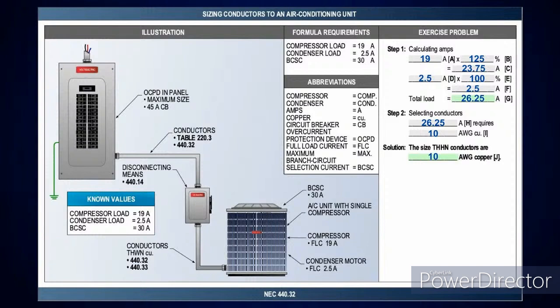Now remember this. You're going to still take one motor at 125% and all the rest are added at 100%, which you'll really see in the next illustration. So the largest motor here is the compressor. I'm going to take it at 125%. That'll give me 23.75 amps. Then I'll take the condenser, which is 2.5, at 100%. Add that together, it gives you 26.25 amps. Then I go to table 310.16, and the next size above that in the 75 degree C column is 30 amps, which is a number 10 copper conductor.